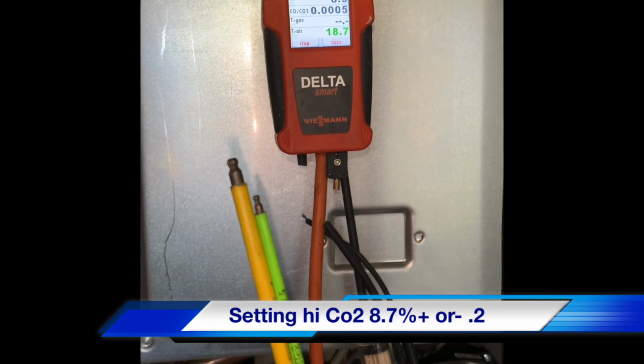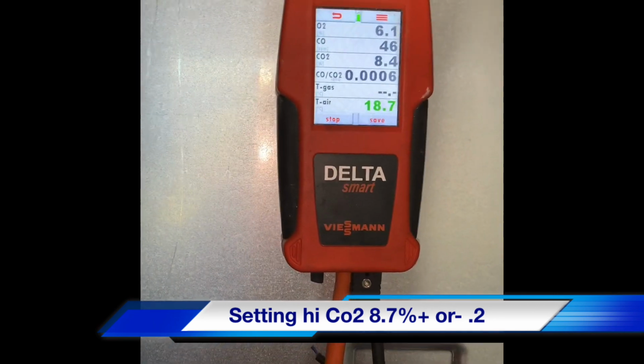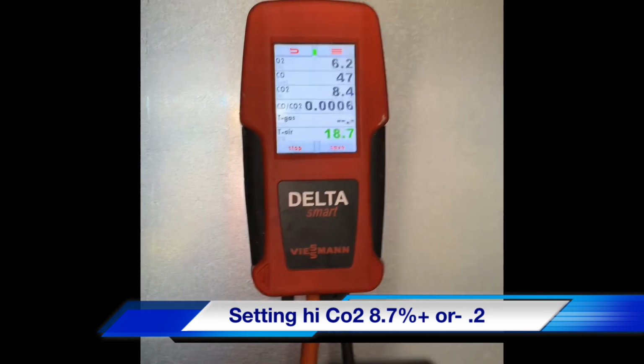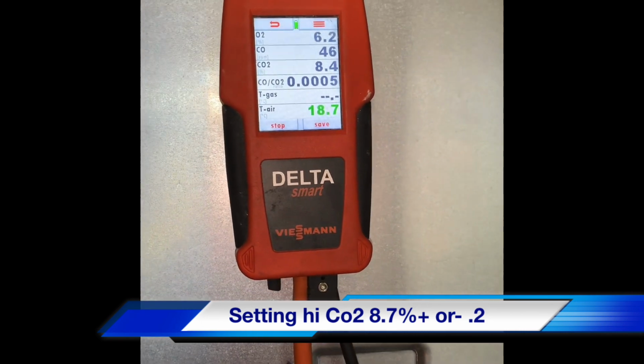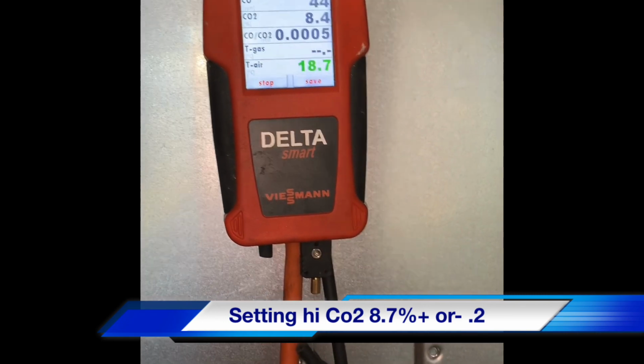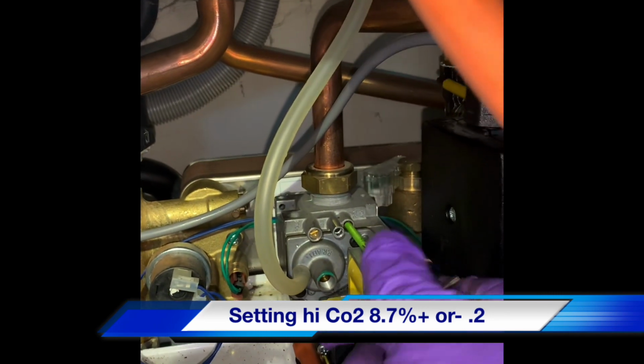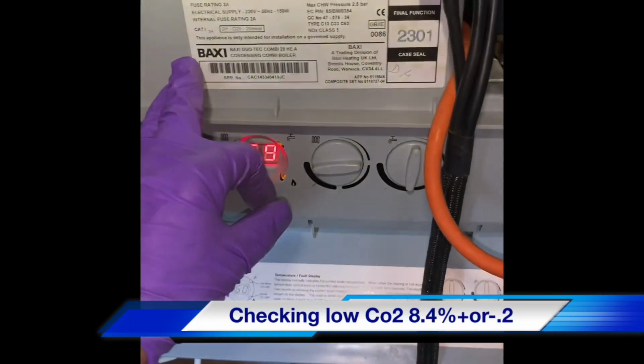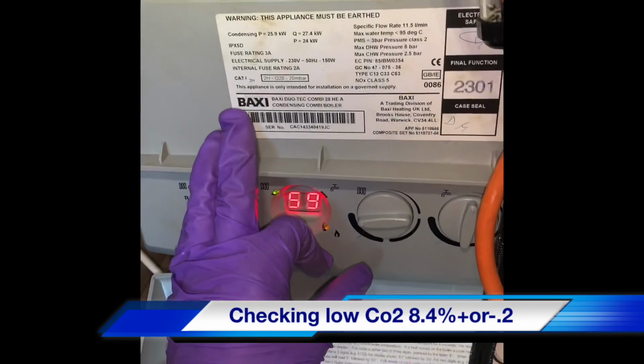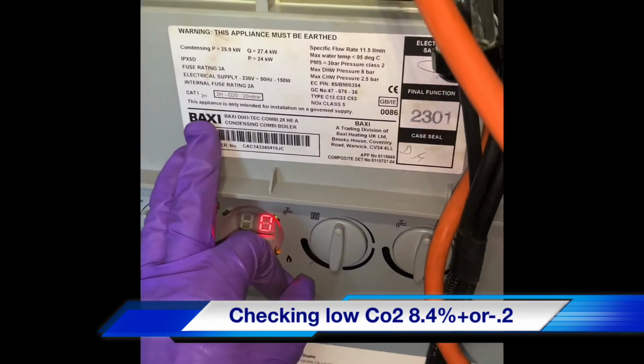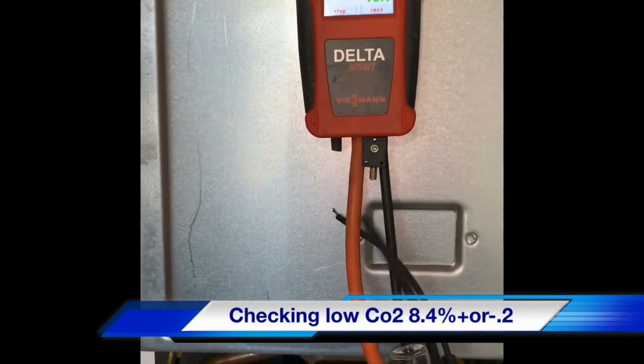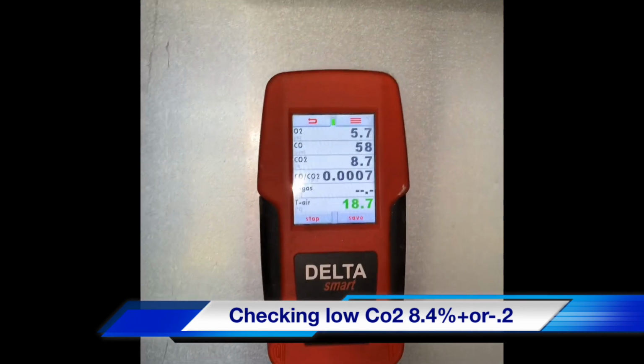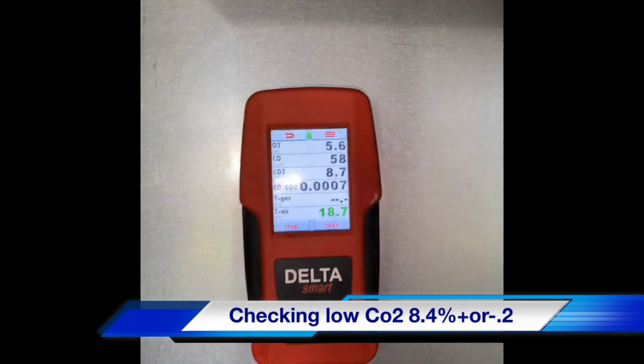To adjust these, you will need a 2.5mm Allen key and a 4mm Allen key. And as you can see, my high is just a little bit low, so we need a bit of minor adjustment. We're now going to check the low CO2 setting. So while it's still in service mode, reduce the boiler potentiometer down, just slow the fan down. We're now looking for 8.4 plus or minus 0.2.